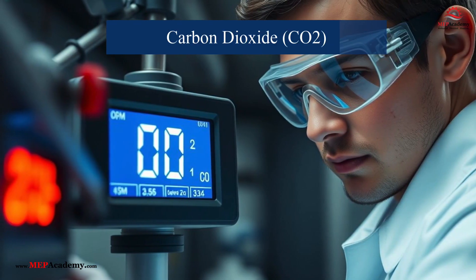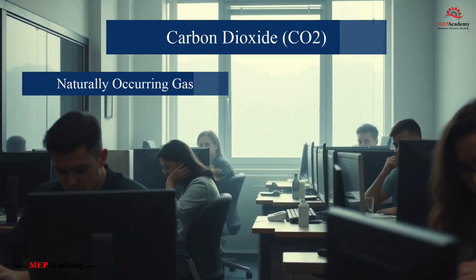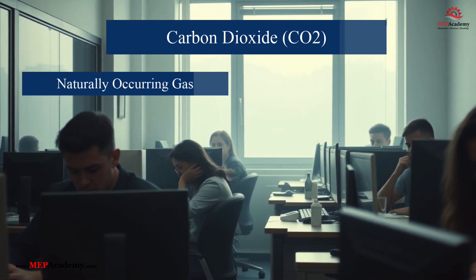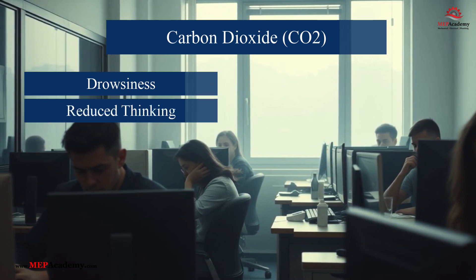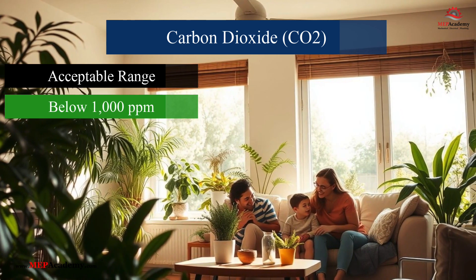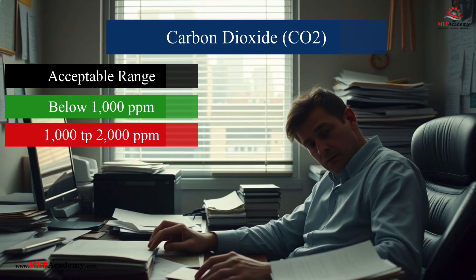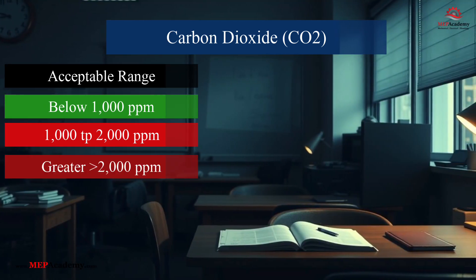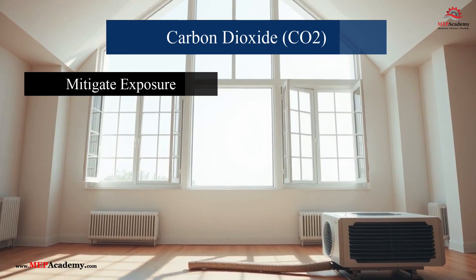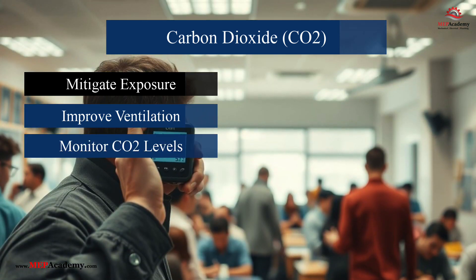Carbon Dioxide (CO2) is a naturally occurring gas produced by respiration and combustion processes. Elevated indoor CO2 levels are often a sign of poor ventilation, which can cause drowsiness, reduced cognitive function, and discomfort. Acceptable Range: Levels below 1,000 ppm are generally acceptable; 1,000–2,000 ppm may cause discomfort; above 2,000 ppm can significantly impair concentration and well-being. To mitigate, improve ventilation by opening windows or using mechanical ventilation systems.